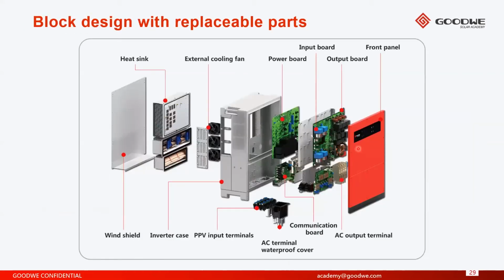The inverters are designed in a way that allows the components to be easily replaced should they become damaged. So if a communication board or the main board was damaged by a surge or a lightning strike, it's quite easy to simply take off the cover and replace the damaged PCB board with a new one. It's also quite easy to remove and replace the fans, which are located on the sides, and the vents as well. The input terminals and the AC output terminals can also be replaced. So in terms of maintenance, it's not so difficult to carry out.